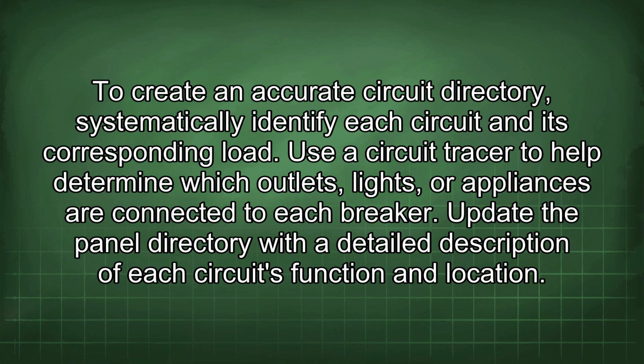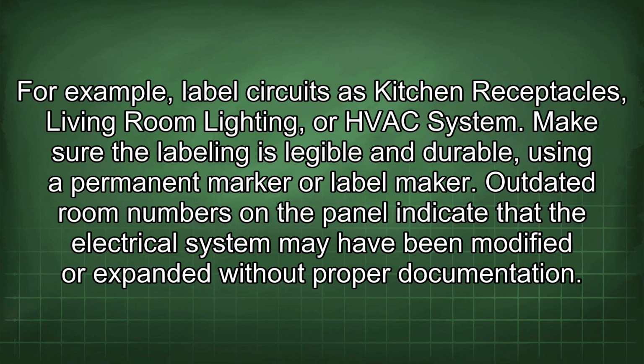To create an accurate circuit directory, systematically identify each circuit and its corresponding load. Use a circuit tracer to help determine which outlets, lights, or appliances are connected to each breaker. Update the panel directory with a detailed description of each circuit's function and location. For example, label circuits as kitchen receptacles, living room lighting, or HVAC system. Make sure the labeling is legible and durable, using a permanent marker or label maker.